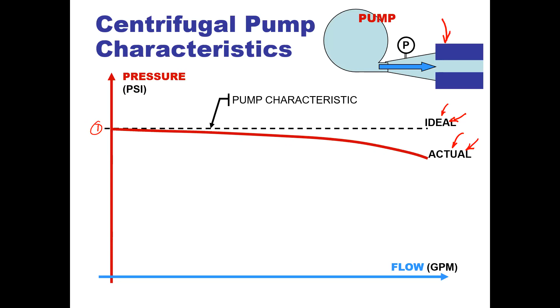This is going to be calculated for whatever our pressure is, what our line loss is, all that information we just went over, all that mathematics I said doesn't really matter in this class. These system characteristics determine where you'll have these system characteristic lines. So at this system, we could see this pipe is, let's say, open 4 inches or whatever. This system characteristic is for like a 4-inch pipe coming out. And it's not just the pipe, it could be going through heat exchangers, it could be going through valves. It's the entire system in and of itself. But it's easiest to think that this is a 4-inch pipe right here.